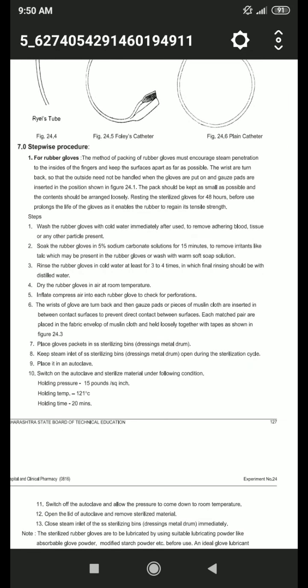Then place the glove packets in an SS sterilizing bin, that is, a dressing metal drum. Keep the steam inlet of the sterilizing bin open during the sterilization cycle. Place it in an autoclave, then switch on the autoclave and sterilize the material under the following conditions: holding pressure, holding temperature, and holding time. Holding pressure is 15 pounds per square inch, holding temperature is 121 degrees Celsius, and holding time is 20 minutes.